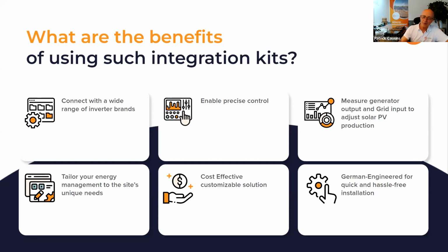So what we do is take an approach which optimizes and reduces that runtime. To do that, we need to know what's happening within the system and then issue commands accordingly. That could mean making sure the rooftop PV continues to operate when running with the generator, without overloading the generator or getting underused. It could also mean deciding what the target state of charge should be at the time the grid fails.